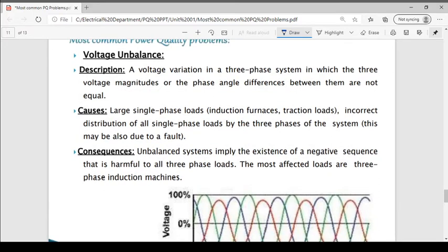Next, let us discuss the voltage unbalance. What is the voltage unbalance? A voltage variation in a three-phase system in which the three voltage magnitudes or the phase angle difference between them are not equal. For a balanced voltage, the R phase, Y phase and B phase have the same voltage magnitude and the same phase angle, that is a 120 degree phase displacement. So the voltage unbalance is different voltage magnitude per phase and a difference in phase angle between them, which is not equal.